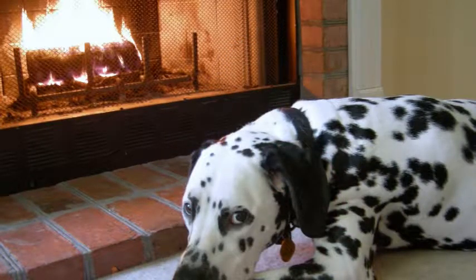And it turned out that what happened is this roofer, he was probably just a handyman, somebody that needed the paycheck, but he had left his tools on top of her chimney flue. And so with his tools blocking the flue, the carbon monoxide that was trying to leave the home through that flue could not, and it killed her. Critter nests. You know, I'd mentioned the raccoons. Sometimes you can get birds in there, whatever it is, and just have that be on your radar.